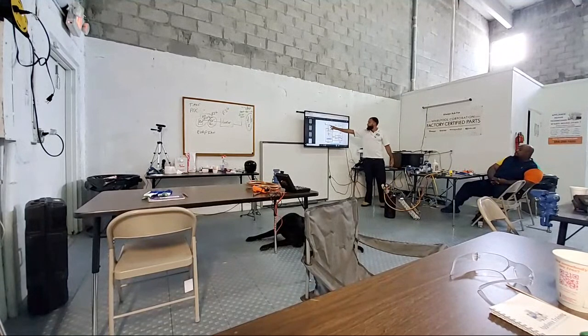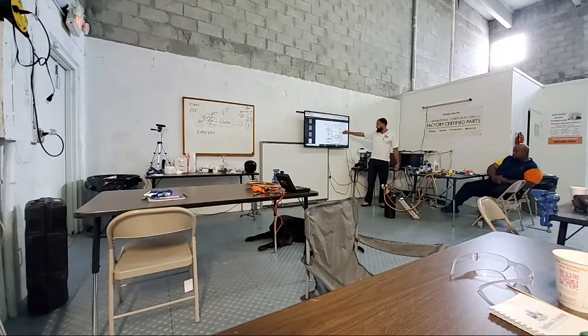I was thinking, because it enters the board, it comes out orange, passes through the thermostat. This is a parallel circuit: condenser fan, compressor circuit, evaporator fan circuit. It goes out to neutral. There's no way for us to check that. Right, so they give us that wire right there on the 6.